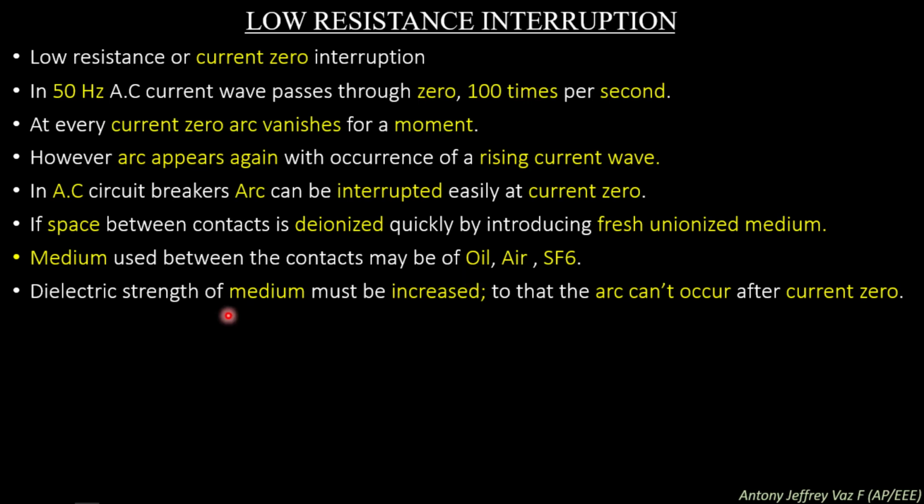The dielectric strength of the medium must be increased so that the arc cannot occur after current zero. So the freshly filled dielectric material should have very high dielectric strength so that the arc cannot restrike back after current zero. If the dielectric strength of the medium is weak, then the rising current wave will make the arc restrike back after current zero for half a cycle.